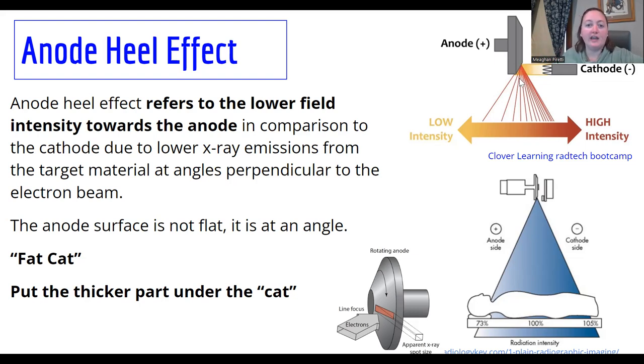And you've probably heard the term fat cat, if you haven't. That just means put the thicker part of the anatomy under the cathode. So what is the thicker, more dense part? And that should go on the cathode side of the beam.